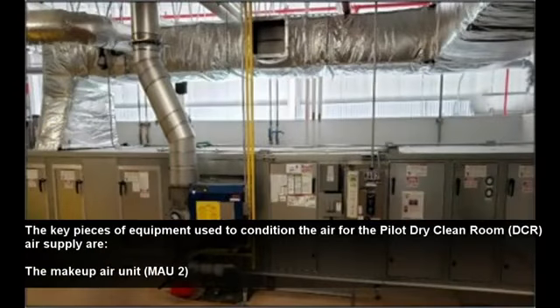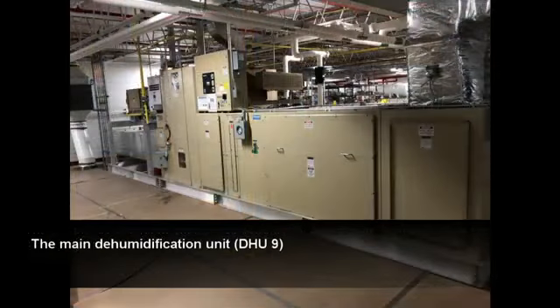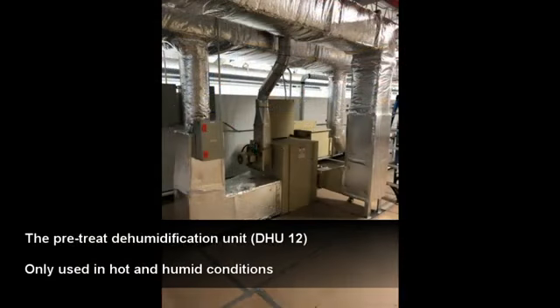So the current system for dry air supply was examined, and the key pieces of equipment used to condition the air for the pilot dry clean room air supply are the makeup air unit MAU2, the main dehumidification unit DHU9, and the pre-treat dehumidification unit DHU12, which is used to supplement DHU9 during the summer months when it's hot and humid conditions. All of these key equipment are located above the pilot DCR in the mezzanine mechanical area.